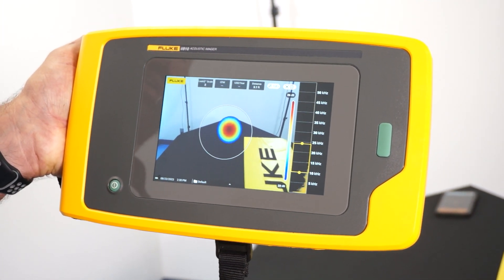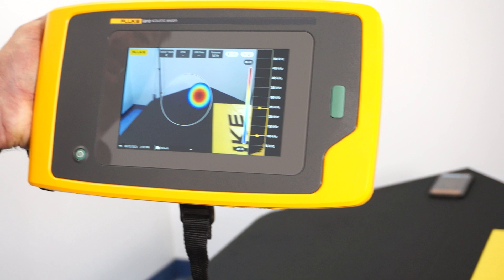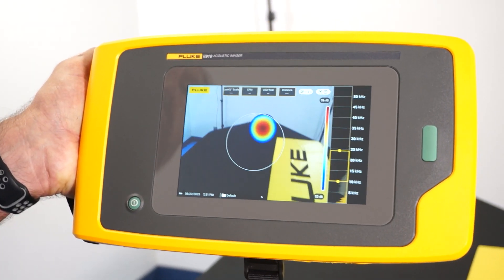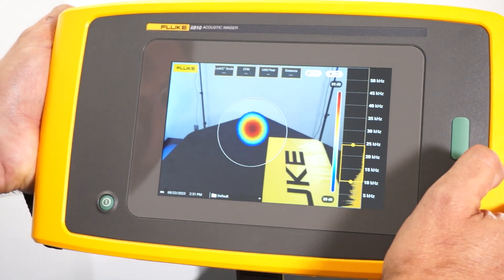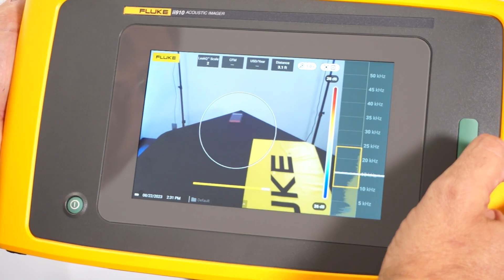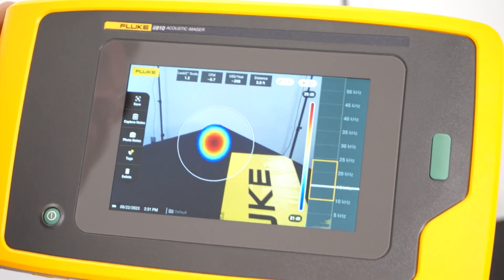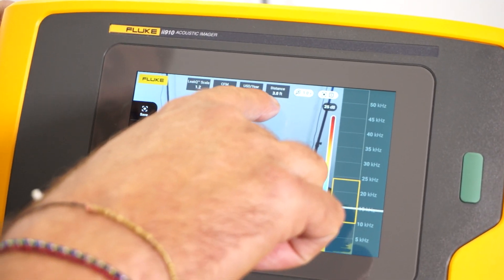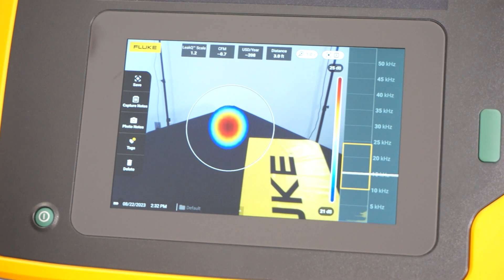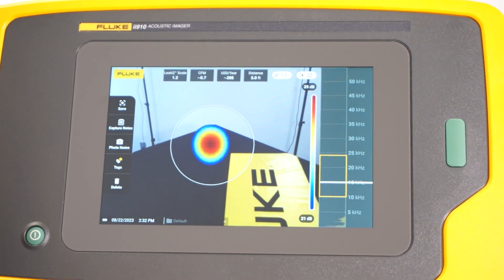What we've done with some of the more recent firmware updates is the ability to do it on the camera itself. I've got a signal generator going on my mobile phone putting out a signal at right about 15 kilohertz. I'm going to aim at the leak, put it in the circle in the middle, and hit the capture button. Once it captures the leak, it's giving me a LeakQ scale of 1.2 — a number we assign as a severity to the leak — a distance to target of 3 feet, a CFM score, and an estimate of about 200 bucks a year. So that quote-unquote leak would be costing us about 200 bucks a year, and that's something we can now do right on the camera.